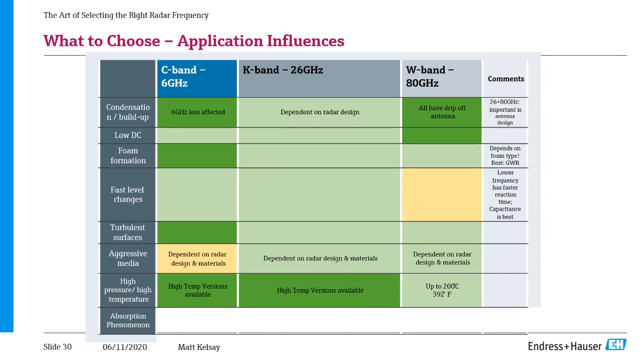High pressure and high temperature was discussed just a little bit. So again, on our lower frequencies, we have the ability to reach higher pressures and temperatures, exceeding 750 degrees, whereas on the W-band radars, all of those radars have more of a Teflon style, so we're limited to 392 degrees F.